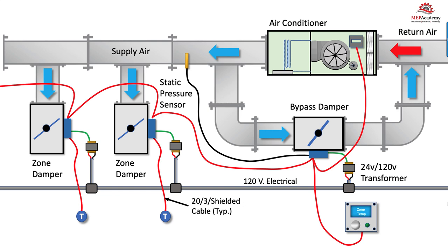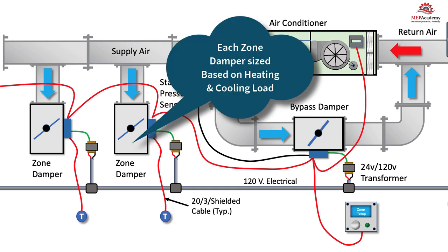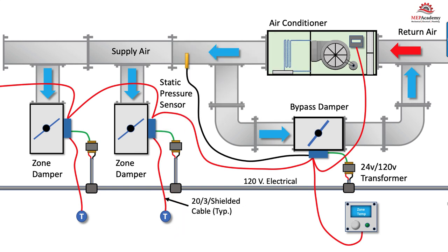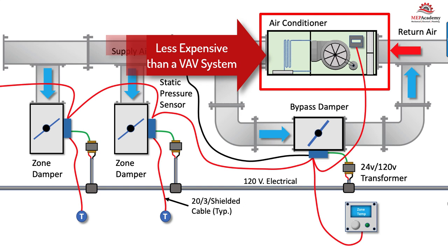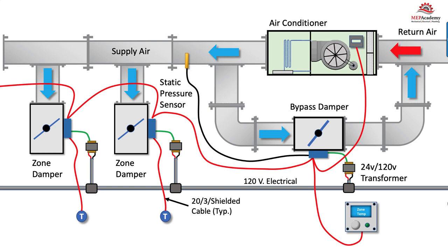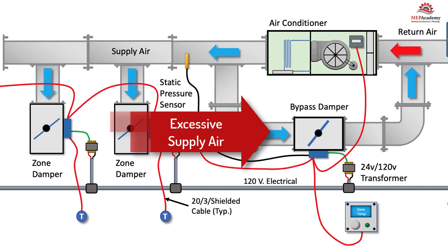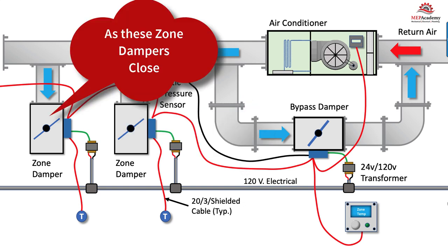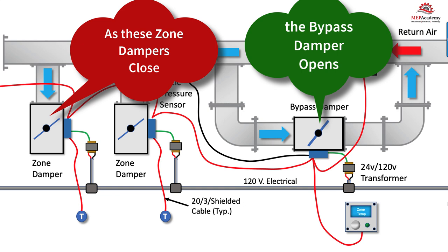A VVT system uses zone dampers so that each zone can adjust the volume of air it receives based on its heating or cooling load. Each zone has its own controller that adjusts the air volume based on demand. What makes the VVT system different from the more efficient VAV system is the use of a less expensive constant volume air conditioning unit and less sophisticated controls. The VVT system uses a bypass controller to modulate the bypass damper to allow any unused supply air to return to the system when zone dampers start to close.